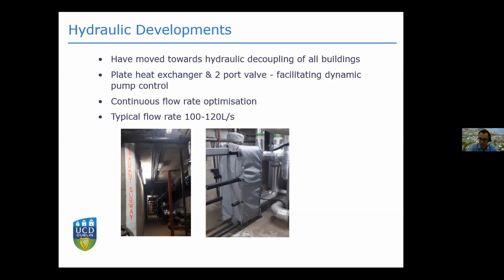That's a space heating plate heat exchanger. We could also have a hot water heat exchanger, depending on the building operation. Typically beside that we'd have a large two-port control valve, which allows us to facilitate dynamic pump control - we can control the flow into that heat exchanger to control the secondary temperatures. That's something we're always monitoring, flow rate optimization.